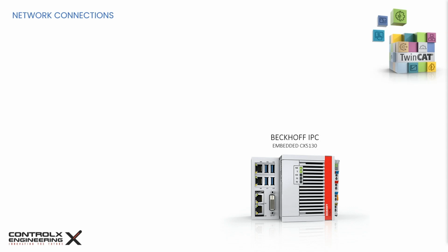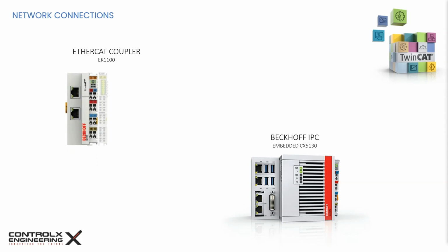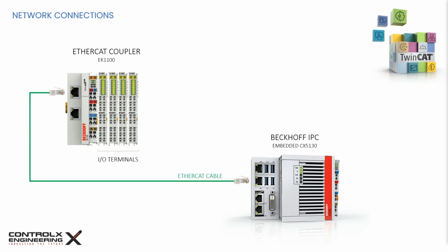Our PLC will be programmed on the CX5130, which is an embedded Intel Atom-based IPC with TwinCAT 3 XAR, or runtime. To form our station to connect the IO terminals, we will use the EK1100 EtherCAT coupler. A station consists of a coupler and any number of EtherCAT terminals that are automatically detected and individually displayed in the process image. A coupler is required in order to connect EtherCAT terminals to an EtherCAT network. This coupler relays the communications from the higher level EtherCAT network to the terminals, or functions as a master itself and generates telegrams. The EK1100 has two RJ45 sockets.